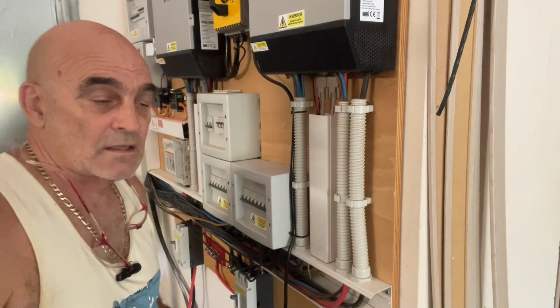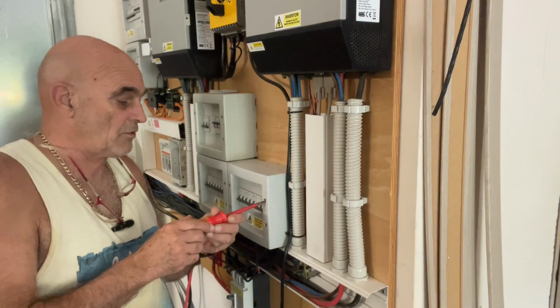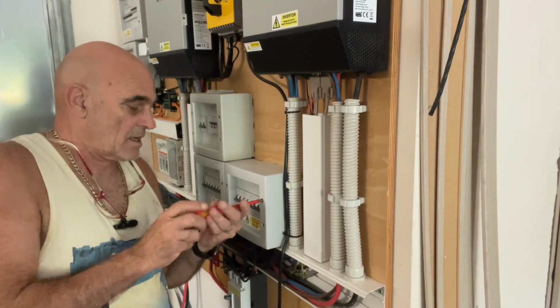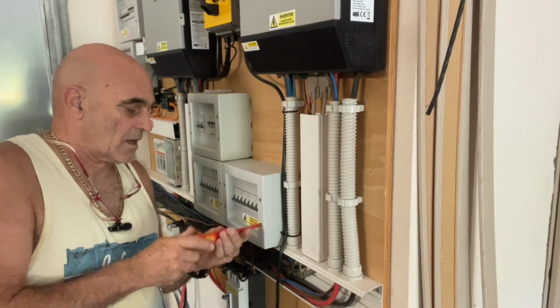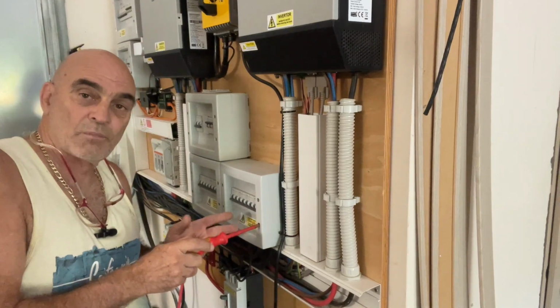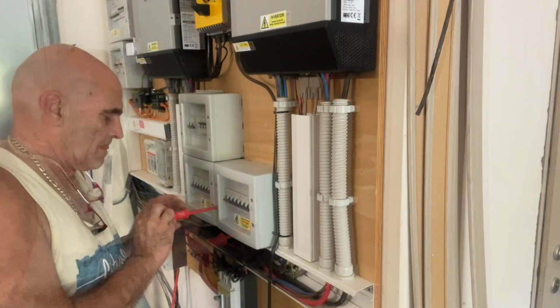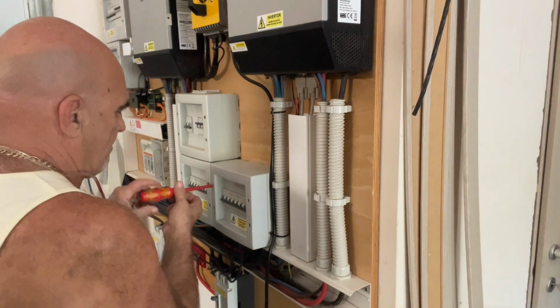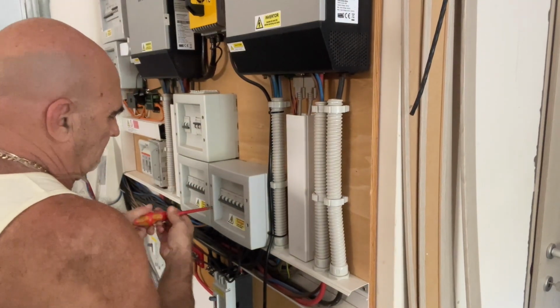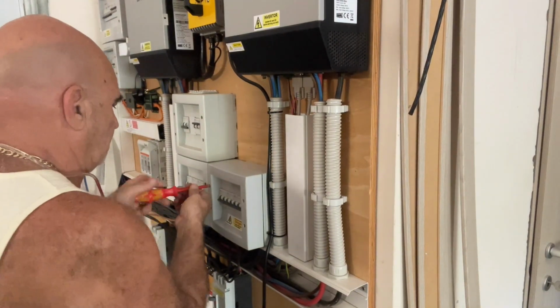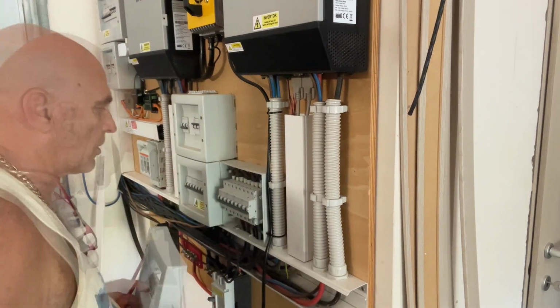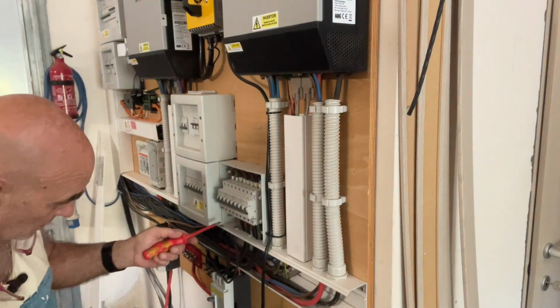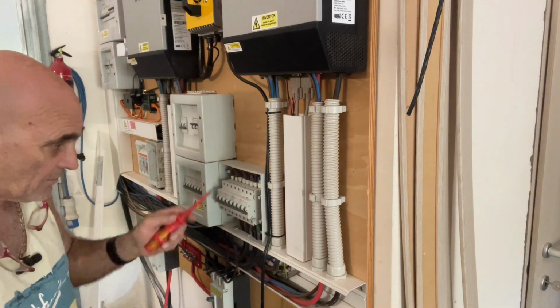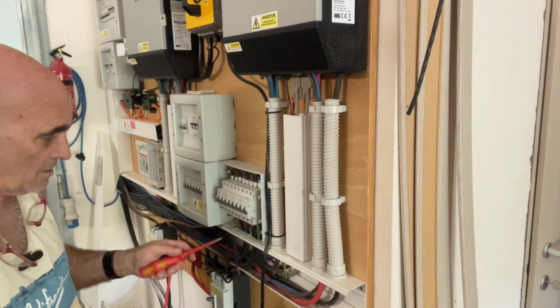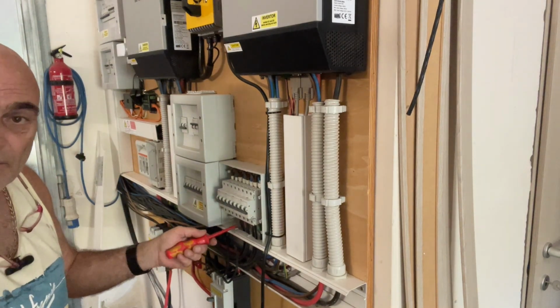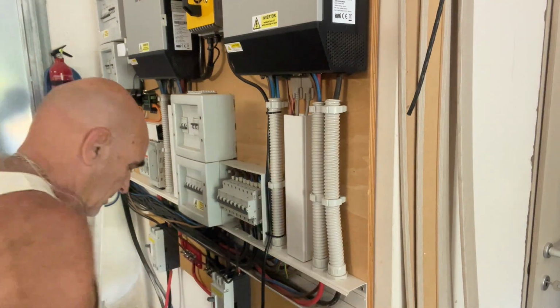Now that I've disconnected the one string on the roof, I need to take these covers off so I can get the multimeter and test each of the strings to see which one's not generating anything, then mark that as the string I want to keep. I've got to be careful here because these are still live even though they're switched off, since that's coming in from the panel side down the bottom.